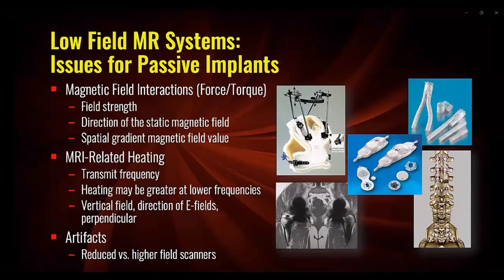Similar to the issues that are present when imaging patients with implants using conventional horizontal field 1.5 or 3 Tesla scanners, there are specific factors that need to be considered when imaging patients with passive implants using MR systems operating at lower field strengths. First, the magnetic field interactions, namely force and torque, are dependent on the strength of the static magnetic field.